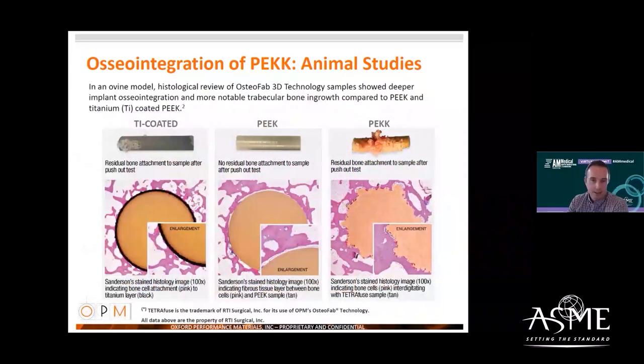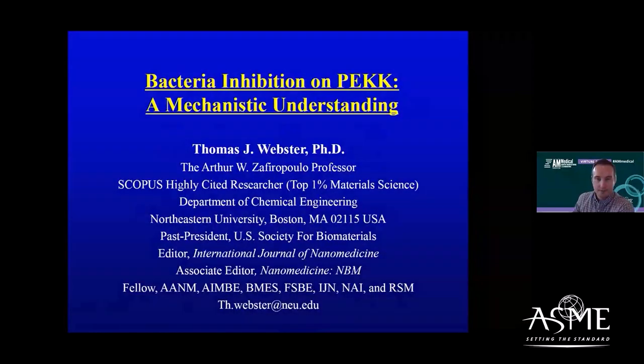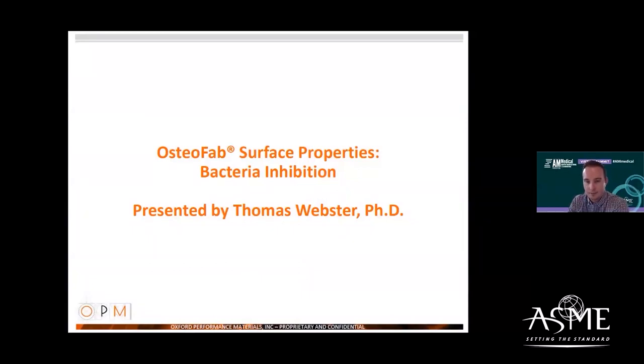A follow-up study looked at the quality of that bone integration using push-out testing. The results clearly show the bone is truly integrated to the PEKK rod — it pulled right out when the rod was removed — versus non-attachment to smooth PEEK and some delamination of the coating on the titanium coated rod, which is an inherent risk with those types of devices. With that, I'll hand it over to Dr. Webster to present the bacteria inhibition studies.